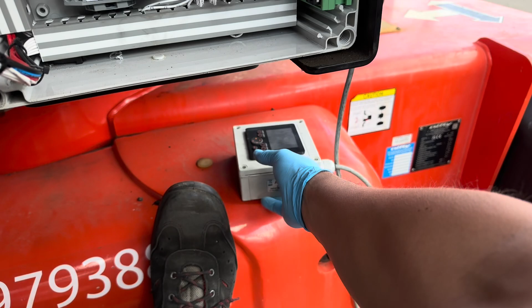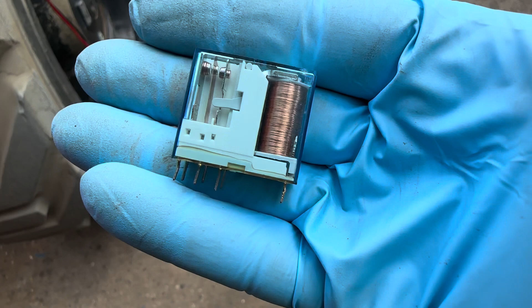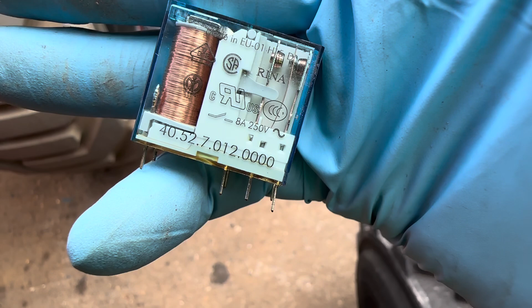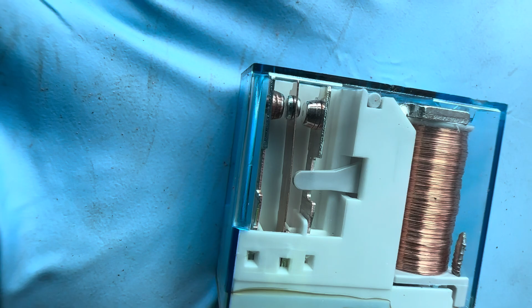The only thing that we had a sounder going off, so I need to check on that. So that relay should stop the continuous beep. It should be alarming instead of continuous beep. Okay, so now I see the problem with this relay here. So the relay K1 is actually, if you look into it, I don't know if you can see it. Yeah, you can. You see how the contact plate is sitting right in the middle, in between, stuck in a limbo. All right, so we need this new relay. It should be like that, and not like that.